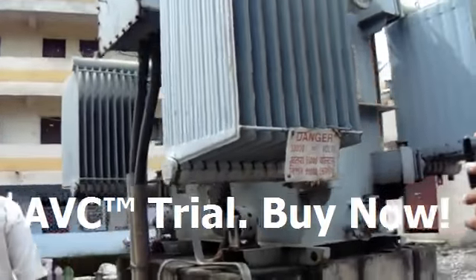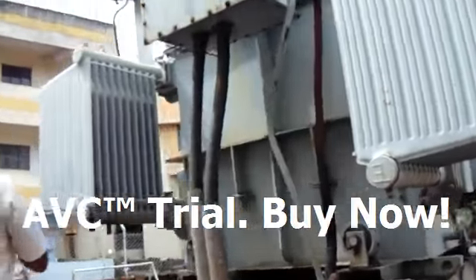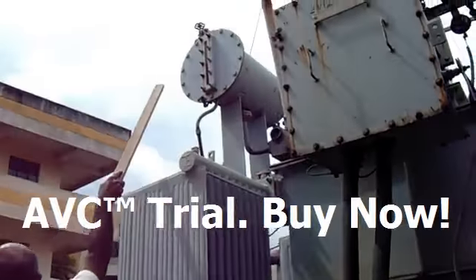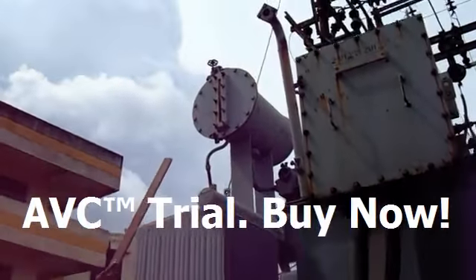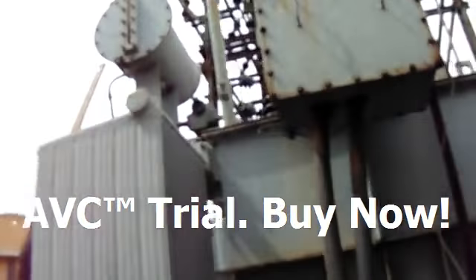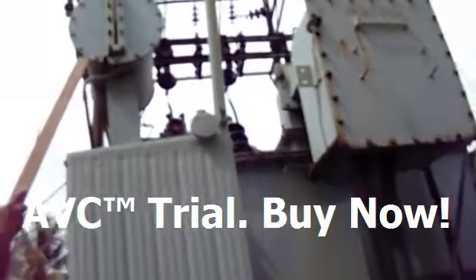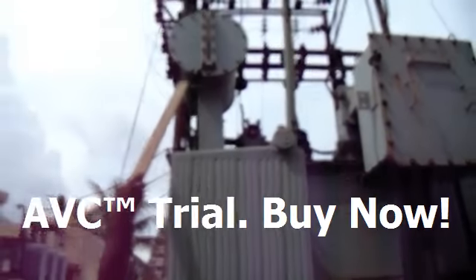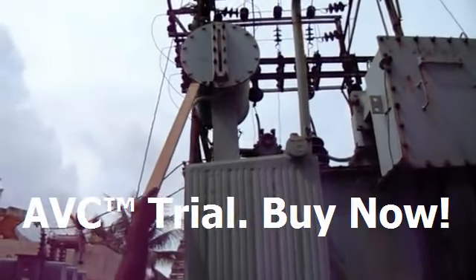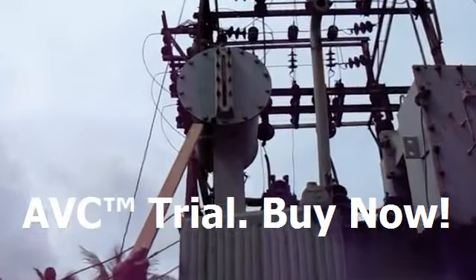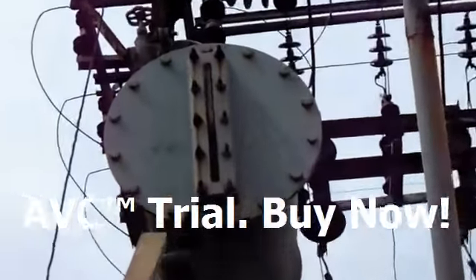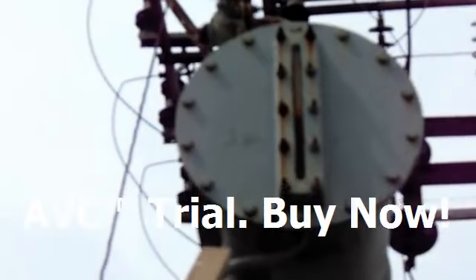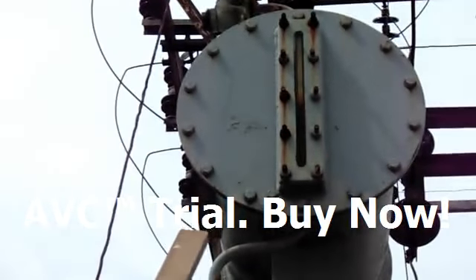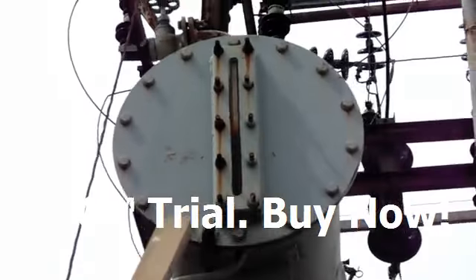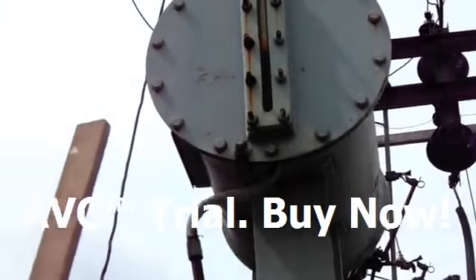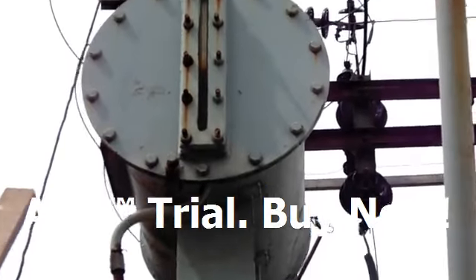Then the other important thing is the conservator tank. This is the conservator tank. The top one is the conservator tank, and you can see the level of the oil. There is a gauge which is given over here. You can see the level of oil which is filled in the transformer tank. Normally, in the conservator the oil should be filled till the half mark, and when it goes down, you have to add extra oil. You have to top up the oil in the transformer.